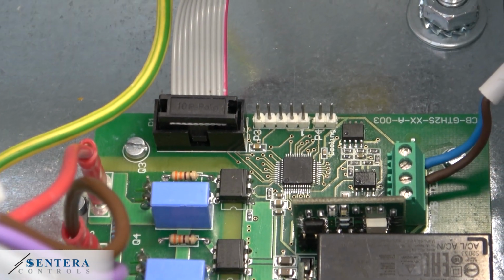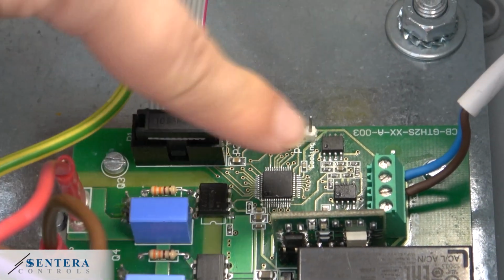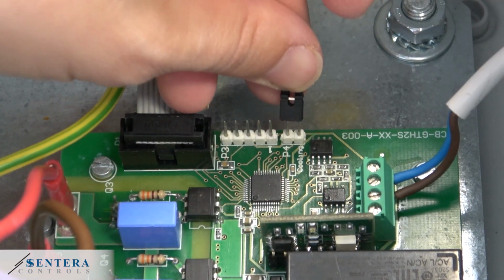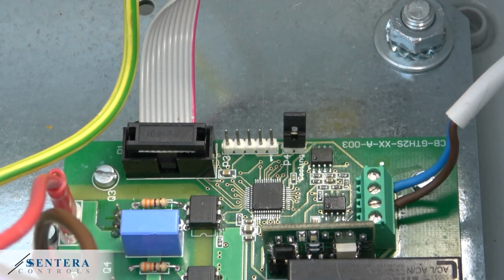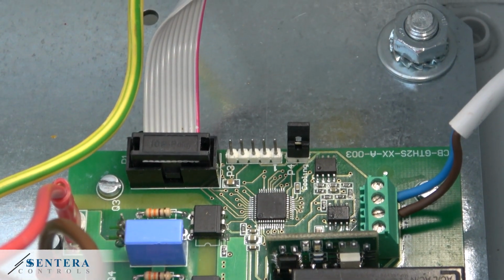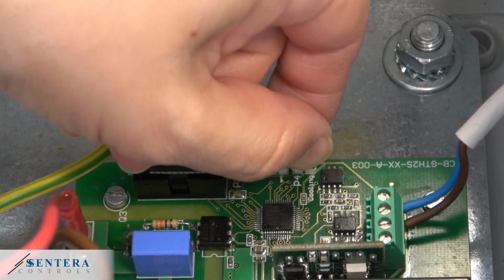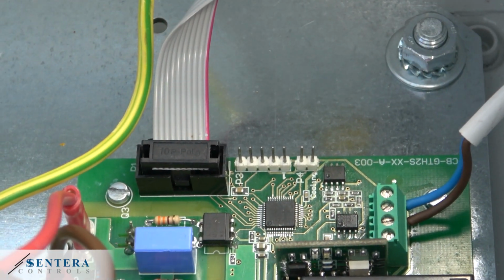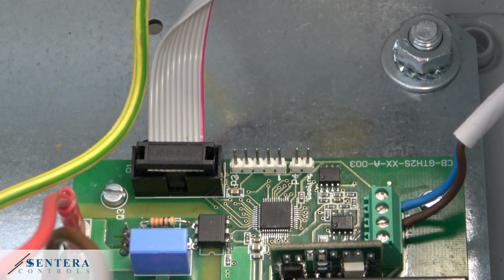Since the controller is intended both for heating and cooling applications, the default mode is heating, and to change it to cooling you will need a jumper that's put on the two pins on the PCB. I'm putting the jumper on the P4 header that's marked with cooling. And this is how cooling mode is activated. Now I'm going to remove it and show you how the controller works in heating mode.